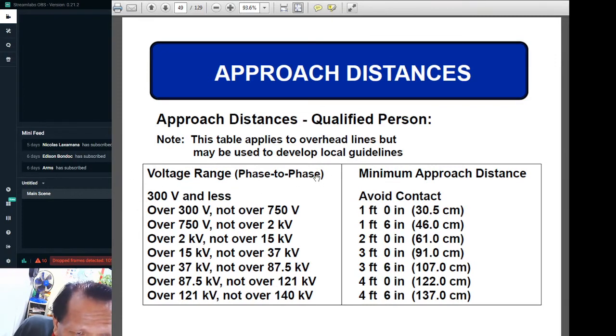So for practitioners, with a voltage range of 300 volts or less, you should not touch it. Never touch it. Higher than 300 volts and not over 750 volts, the distance should be 12 inches, or 1 foot. 750 volts to 2,000 volts is 1 foot 6 inches, or 46 centimeters. 2,000 volts to 15,000 volts is 2 feet, or 61 centimeters. 15,000 volts to 37,000 volts, this is the voltage of the power lines of the Meralco, so it should be 3 feet.